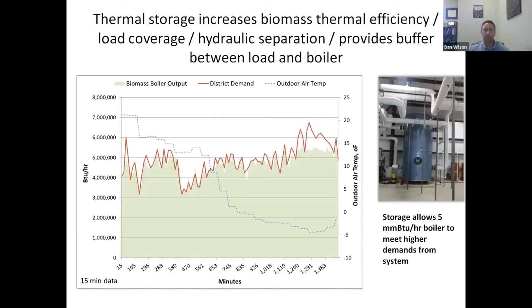It decouples the demands in the facility from the load seen by the biomass or wood chip boiler. That keeps the boiler from cycling, increases efficiency of the overall system, and also lets you meet peak loads above the capacity of the wood boiler itself for short periods of time, which can be very helpful for integration into your facility.